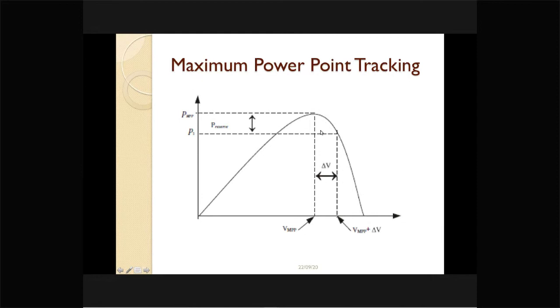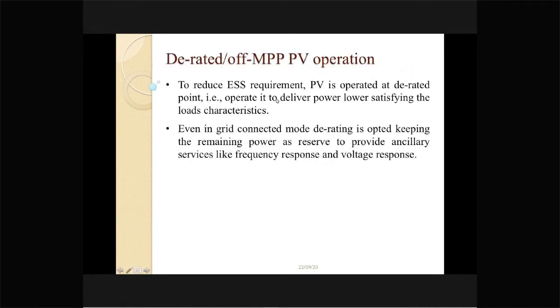So when we do this derated mode of operation, this can be done to achieve certain grid advantages as well, which we'll discuss later on. So this derated mode or off-MPPT PV operation in a grid-connected mode may be required to go for ancillary services like frequency response and voltage response coming from the grid-connected inverters.